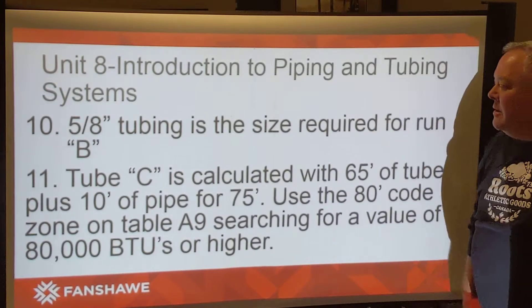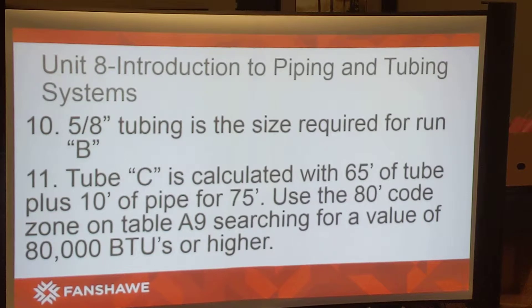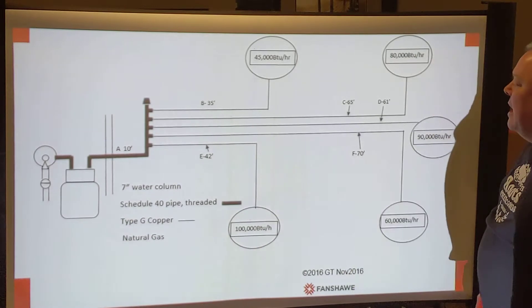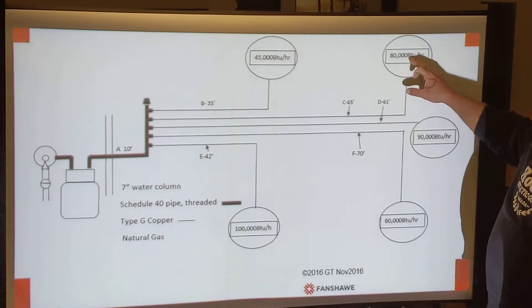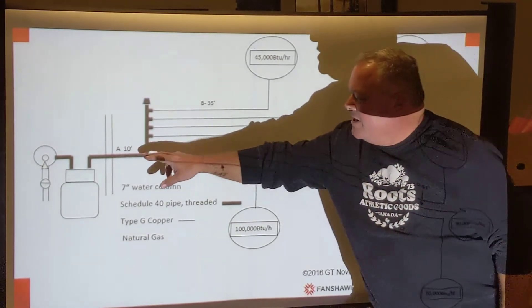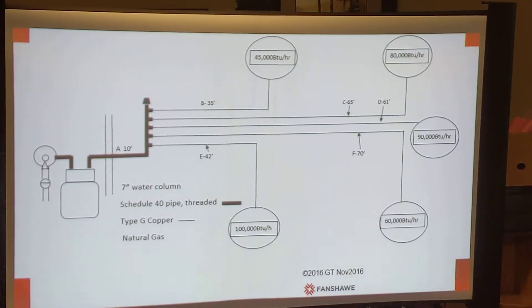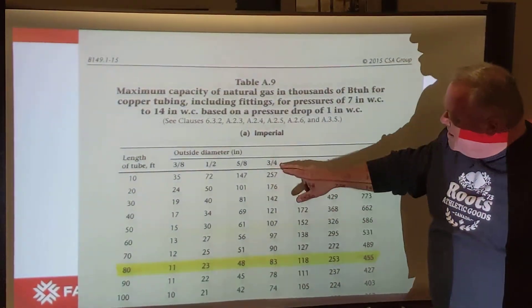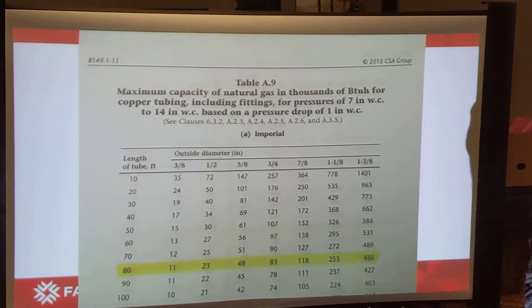Tube C is calculated with 65 feet of tube plus 10 feet of pipe, so our total length is 75 feet. We go to the 80-foot code zone on Table A9, searching for a value of 80,000 BTUs or higher. At the 80-foot level, three-quarter inch just handles it at 83,000 BTUs, so three-quarter inch is the size for tube C.